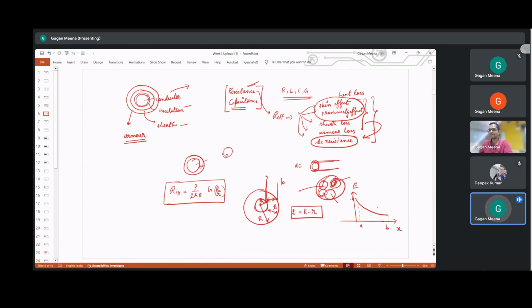So E max, do you remember the formula? If the voltage of the conductor is V, the sheath is always grounded, so it is at 0 potential, and the conductor is at potential V. E max is given by V divided by r ln(R/r), and E minimum is given at capital R. So this is E max and this is E min here.